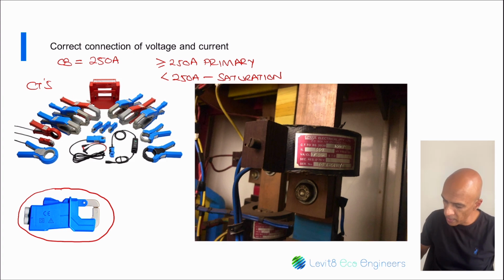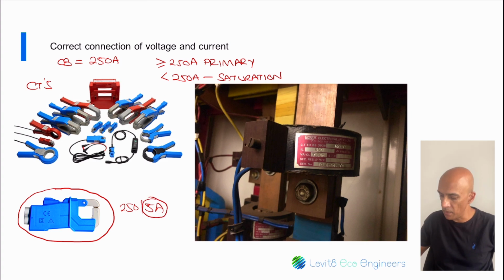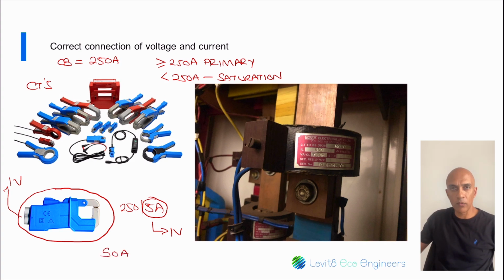So what happens is I'm measuring a 250 amp to 5 amp feeder. So I clip this onto the 5 amp side, which is normally the small wire, 2.5 millimeters squared or whatever AWG. I'm not sure what's the gauge rating for 2.5 millimeters squared. And that in turn will output 1 volt. And then my instrument software then converts this back to 5 amp. Now with 250 to 5, my CT ratio is 50 amp. So when I export my data into Excel, then I would take the output of the 5 amp side and I would multiply it by 50. So if I'm measuring 3 amps, then I'm getting 150 amps on the actual feeder.